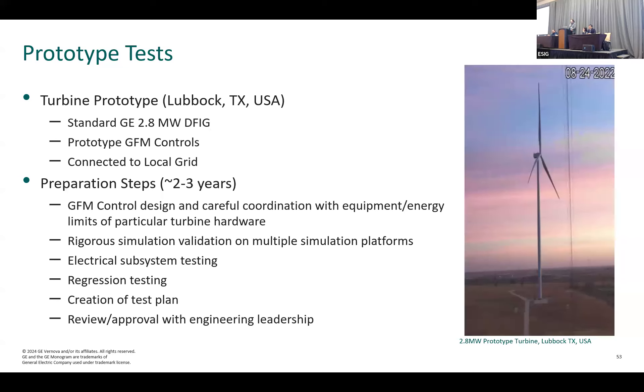On the bottom is a summary of steps taken over three years to reach this point. The prototype controls were first designed — thinking about core control, energy management, power management. We went through rigorous simulation validation platforms using both in-house and external simulation tools. We did electrical subsystem testing in a lab — removing the mechanical part and bringing the down-tower assembly in. Then regression testing connecting the mechanical loading, and then interacting with the drivetrain to make sure everything works as intended with no additional torque stresses.